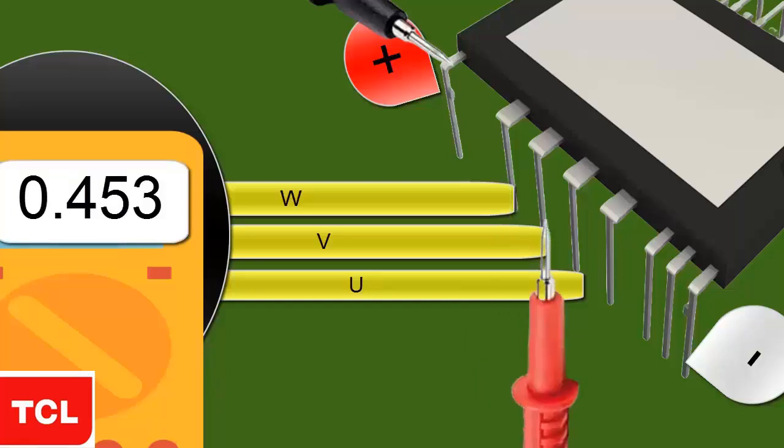The minimum voltage activation values should be around 0.45 volts for each measurement. The measurement obtained between the negative supply and each pin, UVW, should yield practically the same reading.